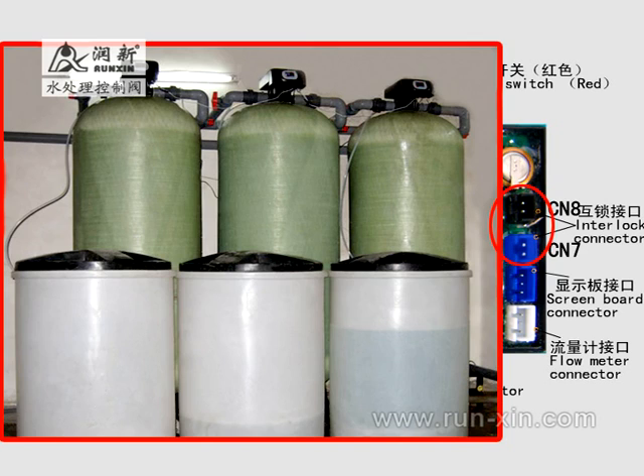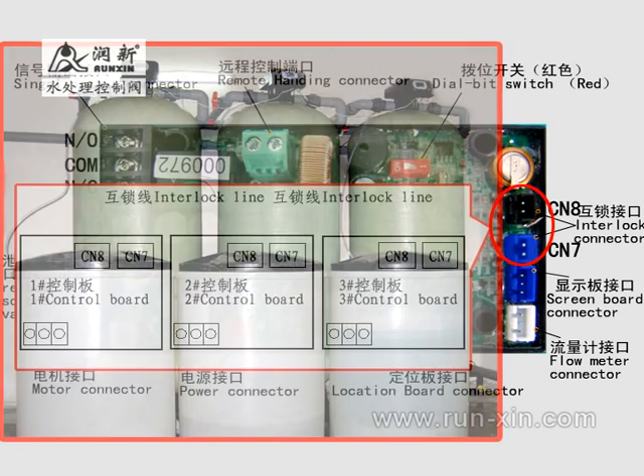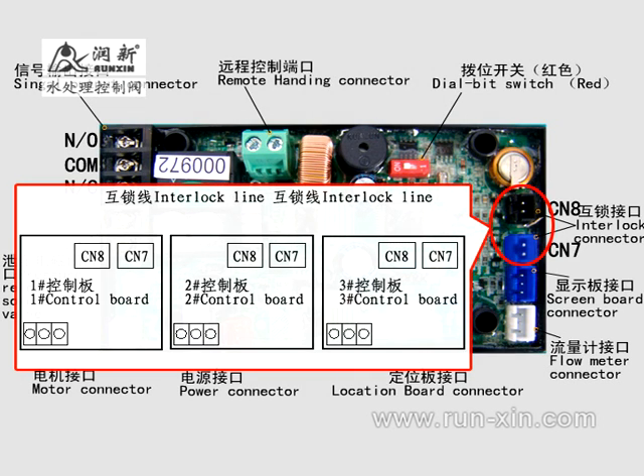In a system of multi-steps, in series or parallel or mixed, in order to avoid 2 or more valves in regeneration at the same time, the interlock function could be used. Find the interlock connectors CN7 and CN8 on the main control board. Use the interlock wire to connect CN7 and CN8.